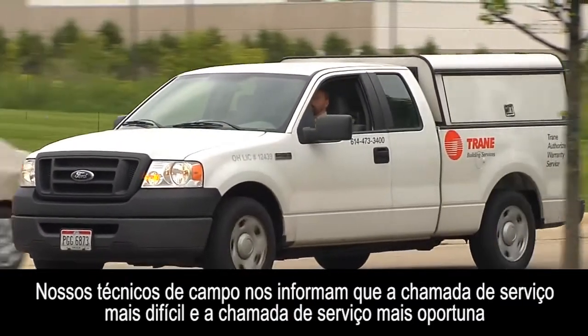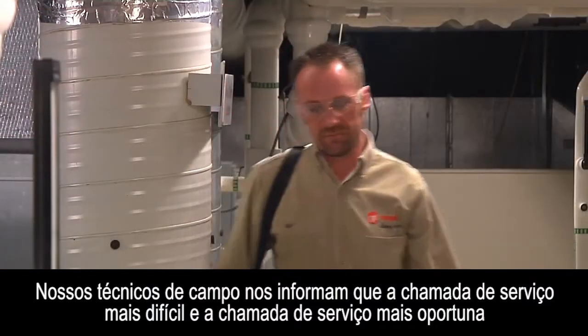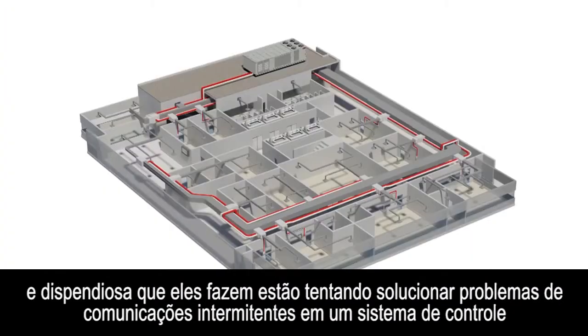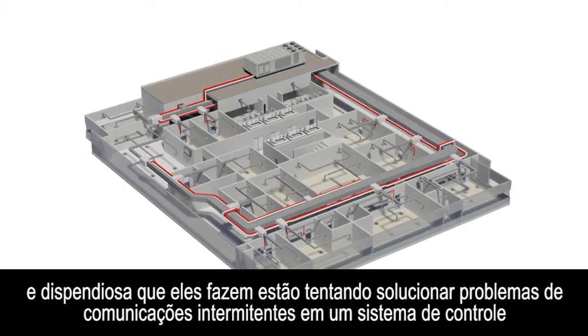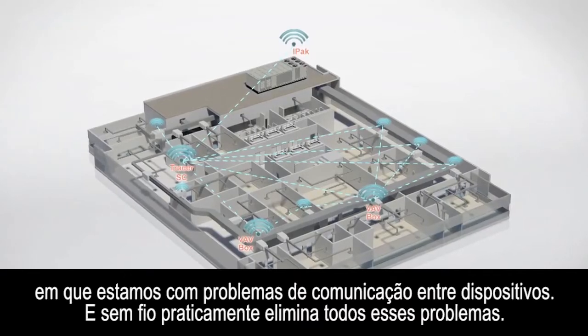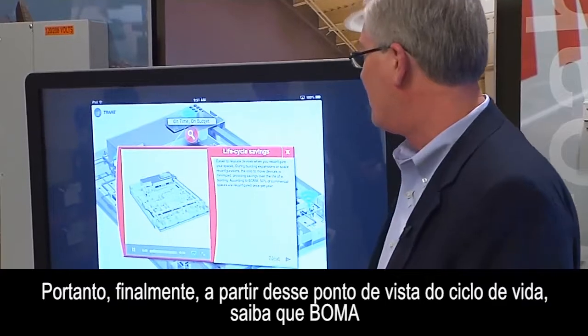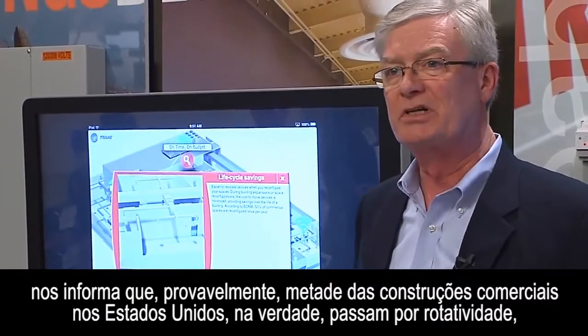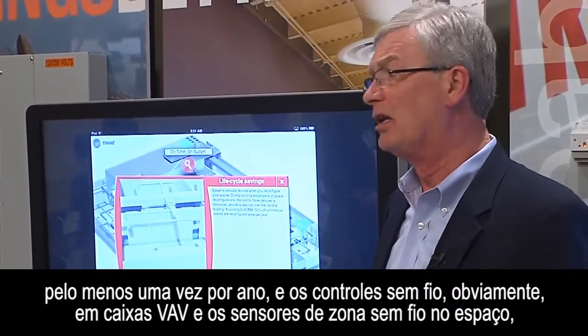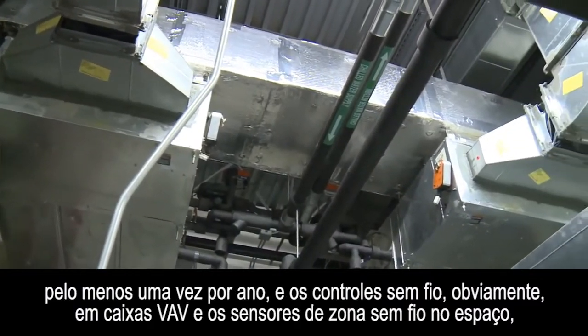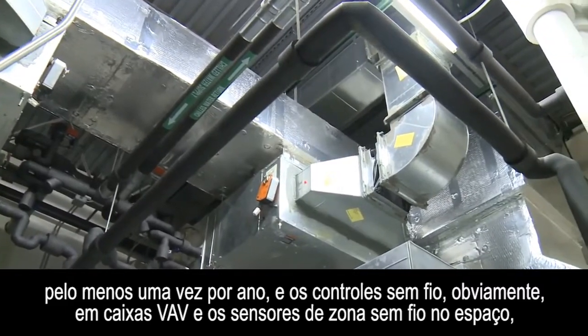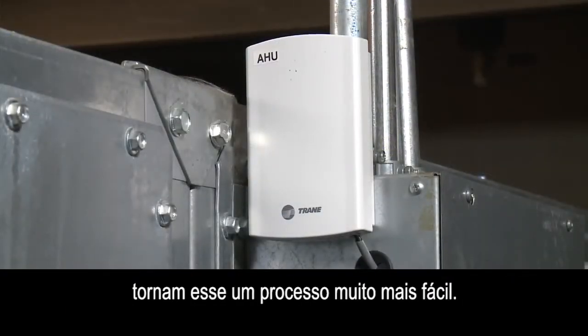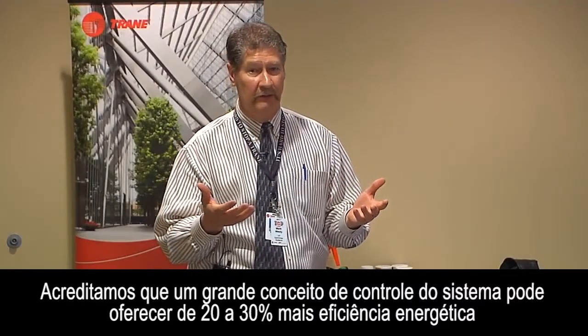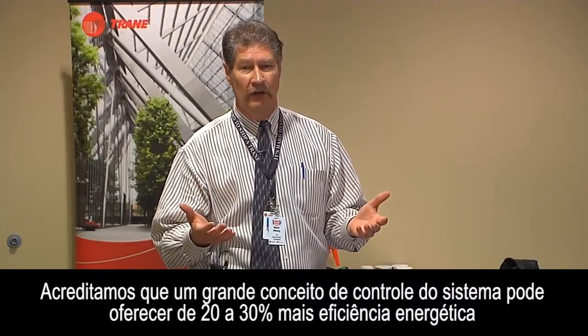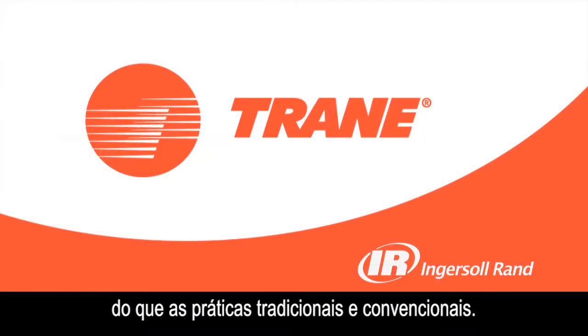Our field technicians tell us that the hardest service call they make and the most timely and expensive service call they make is trying to troubleshoot intermittent communications on a control system where we're having communication problems between devices. And wireless virtually eliminates all of those problems. And then lastly here, from a life cycle perspective, BOMA tells us that probably half the commercial buildings in the United States actually go through churn at least once a year. And obviously, wireless controls on VAV boxes and wireless zone sensors in the space make that a much easier process. We believe a great system control concept can deliver 20 to 30% more energy efficiency than traditional standard practices.